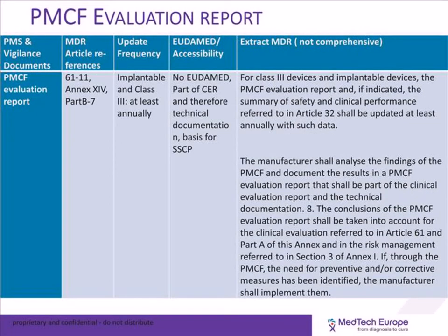Coming next is the post-market clinical follow-up evaluation report. The PMCF plan itself needs to be approved by the notified body and to be proportionate with the risk of the device. The results are processed in what is called the post-market clinical follow-up evaluation reports. So this report will feed some of the other reports we reviewed, such as the CER, the clinical evaluation report.